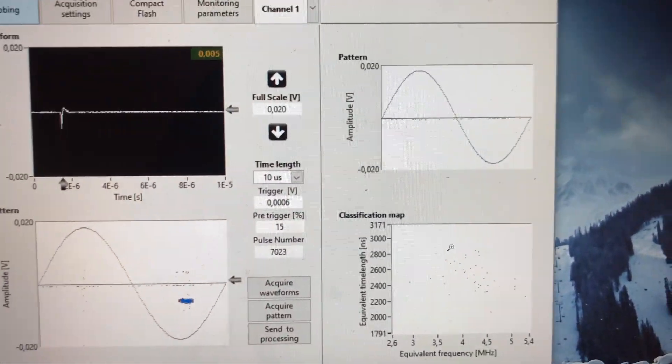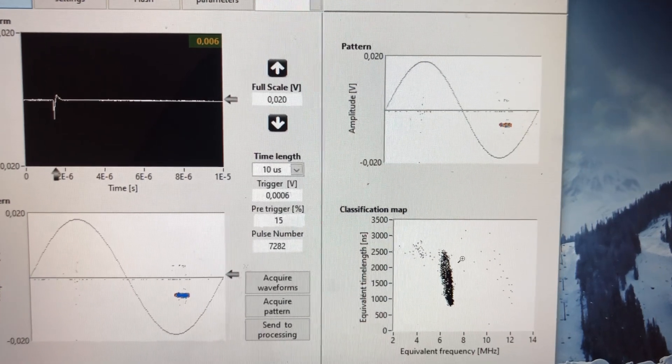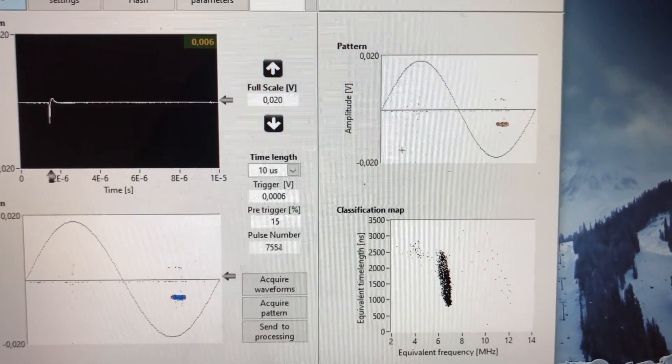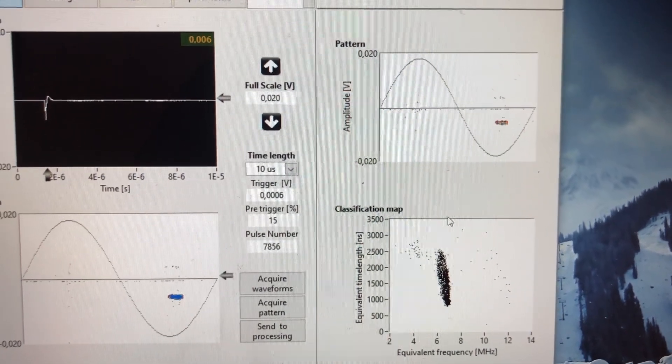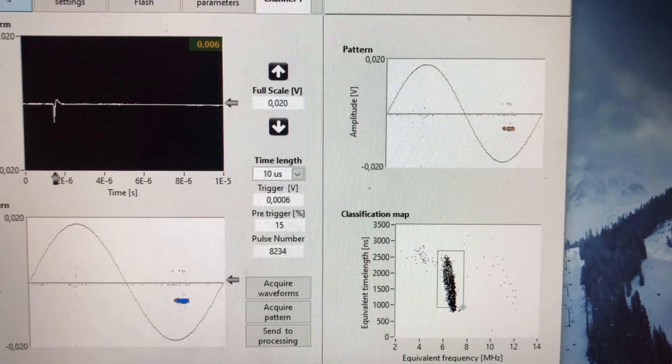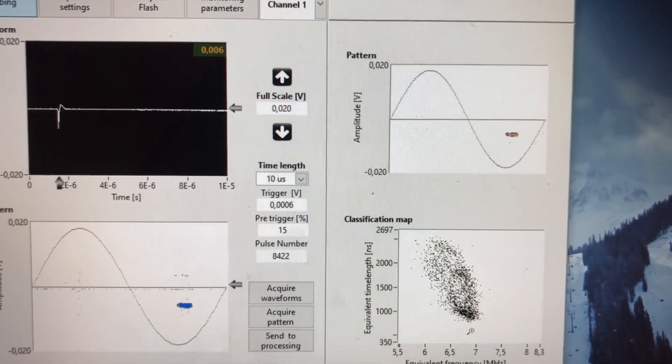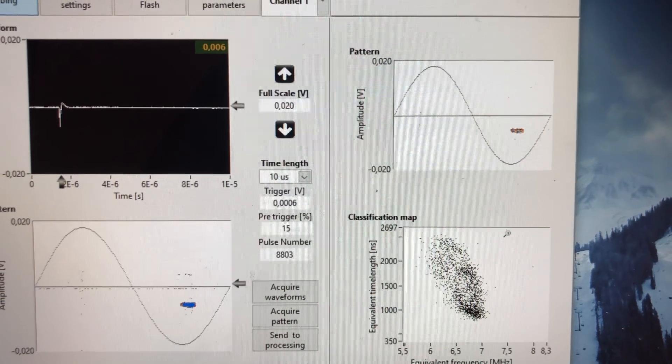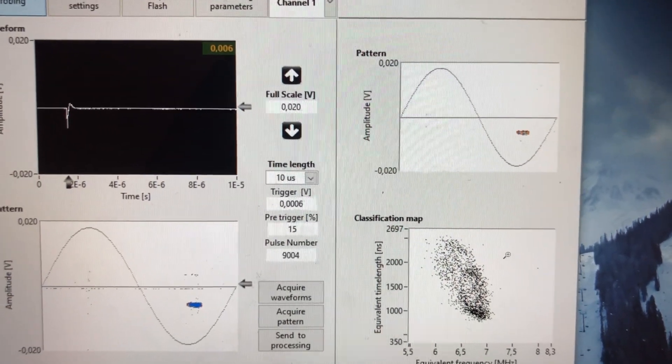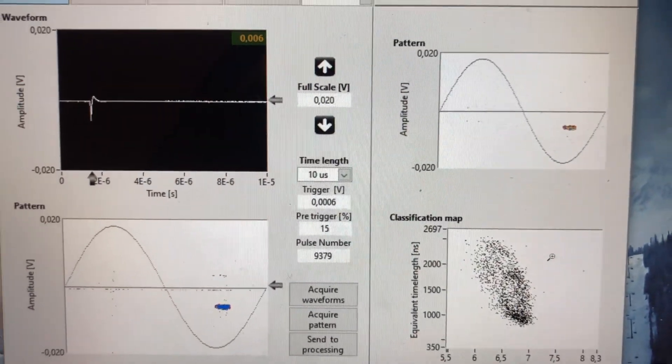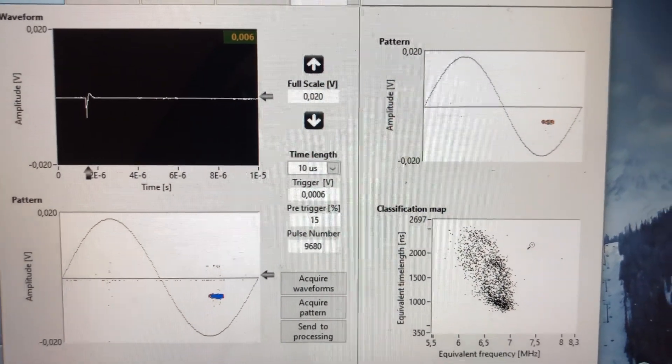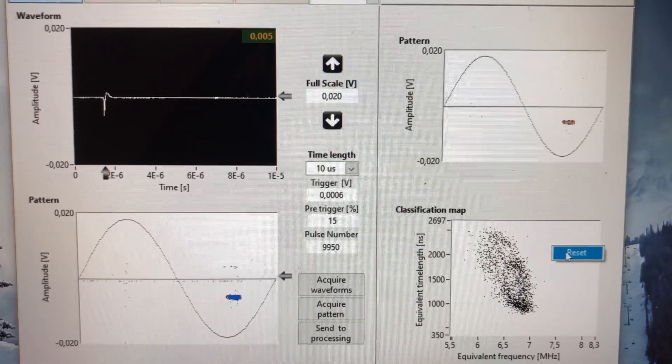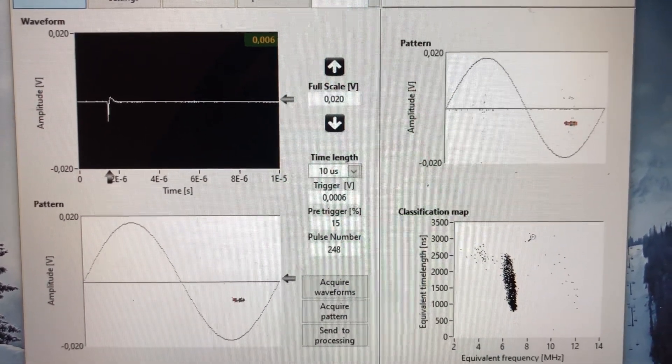So I reset, I go back and then I see this is the noise which is very close to the X axis. The next step is choosing this cluster, which is also quite big. And this is actually the Corona signal. So this is how you can separate two types of signals, which is very useful, especially if they have similar amplitudes and similar phase shifts. Then they can be easily overlapping and we don't want that to happen.